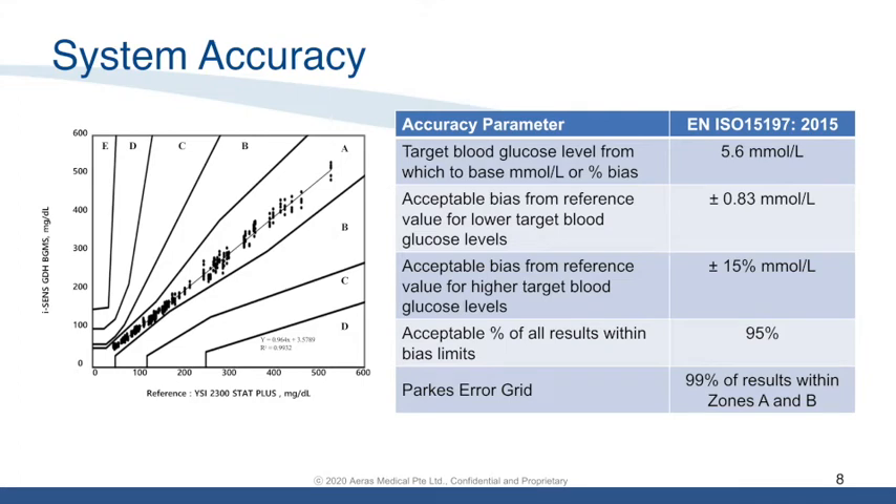This slide provides details of the system accuracy and compliance to ISO 15197:2015. The ISO standard states that the acceptable bias of blood glucose values below 5.6 mmol/L is plus or minus 0.83 mmol/L, while the acceptable bias for values above 5.6 mmol/L is plus or minus 15%. Research shows that 95% of all results obtained for Nipro Premier Alpha meet this requirement, and 99% of results also fall within Zone A and Zone B of the Parkes error grid.